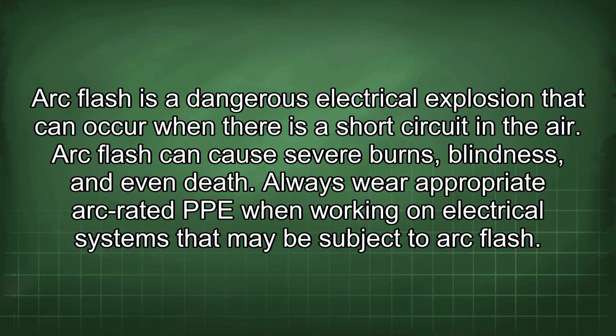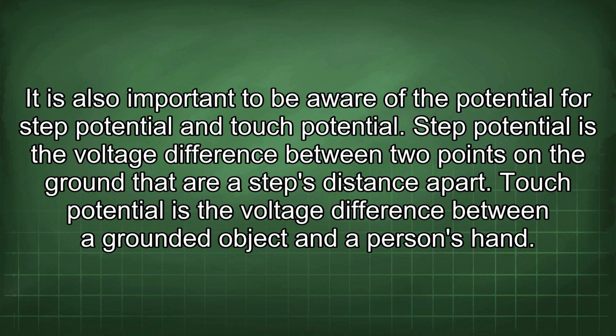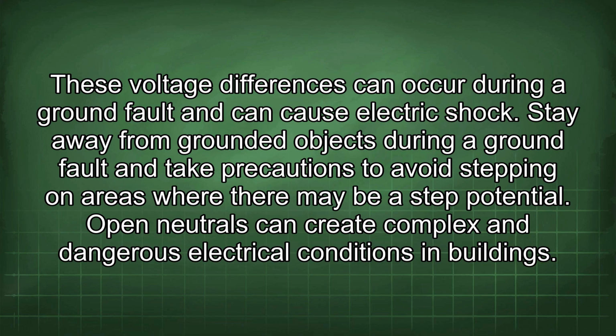Arc flash is a dangerous electrical explosion that can occur when there is a short circuit in the air. Arc flash can cause severe burns, blindness, and even death. Always wear appropriate arc-rated PPE when working on electrical systems that may be subject to arc flash. It is also important to be aware of the potential for step potential and touch potential. Step potential is the voltage difference between 2 points on the ground that are a step's distance apart. Touch potential is the voltage difference between a grounded object and a person's hand. These voltage differences can occur during a ground fault and can cause electric shock. Stay away from grounded objects during a ground fault and take precautions to avoid stepping on areas where there may be a step potential. Open neutrals can create complex and dangerous electrical conditions in buildings.